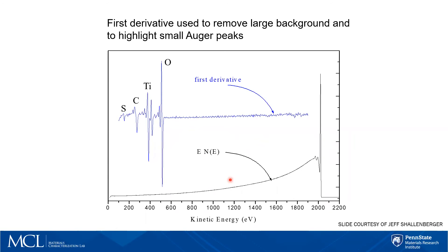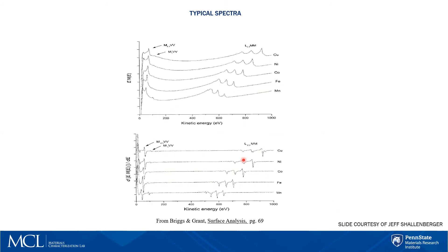The easiest way to remove the background is to take the first derivative of that spectrum. If we take the first derivative of this distribution, we get the spectrum in blue where our elemental peaks jump out at us with a lot more definition. The peak to background ratio in this derivative spectrum is much higher than it is in the raw spectrum, and the derivative has very nicely removed the large, slowly varying background. Every element has its own characteristic set of Auger peaks, and that's how we use the technique for elemental analysis.